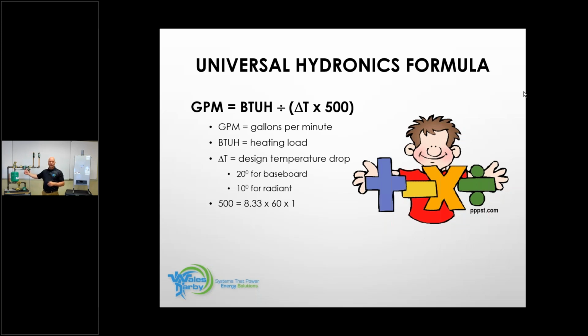If I know the flow rate of this circulator, and let's say I look at the piping, I'll give you a chart here in a minute, and say this is going to be 3 to 4 gallons a minute, let's say 4 through 3/4 pipe. So 4 and 4 is 8 gallons a minute. It's a cast iron boiler, so I'm going to calculate a 20-degree delta T. Now where my GPM is, you can put an 8 over the top of that. You can take the 20 times 500, still equals 10,000. Now I'm going to take my 8 and multiply it by 10,000. That tells me that I should have at least an 80,000 BTU boiler.